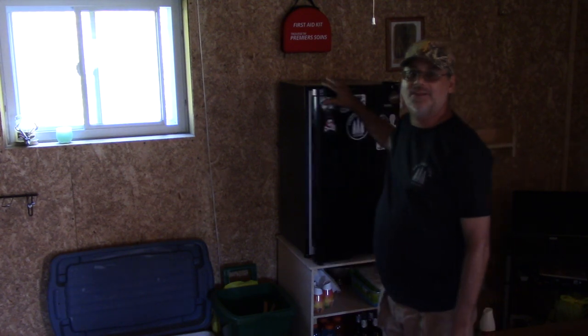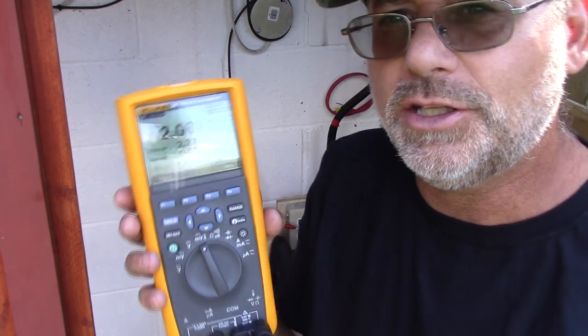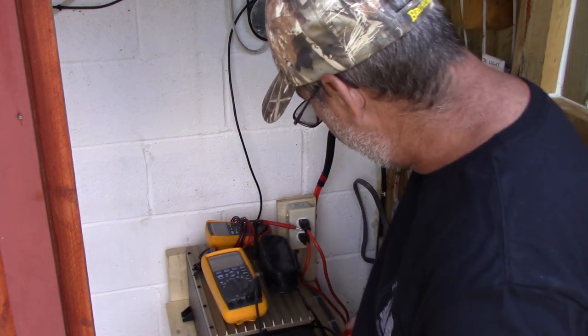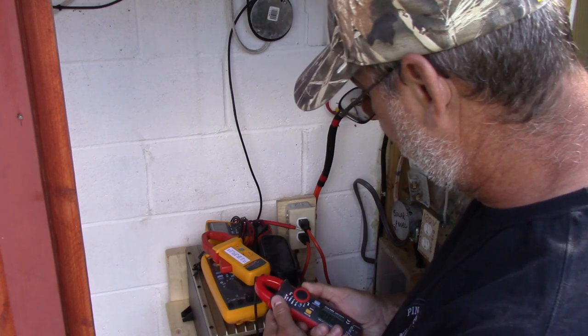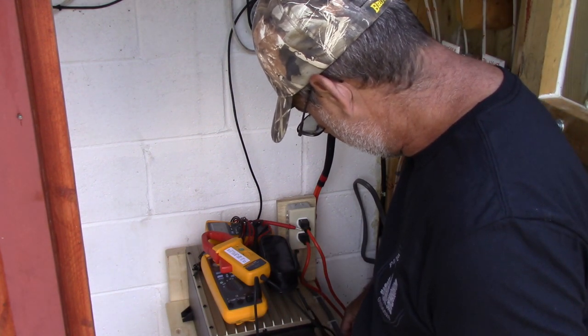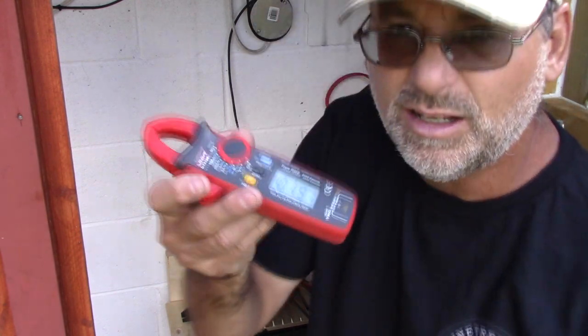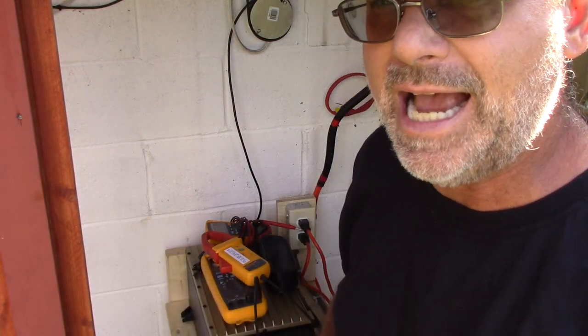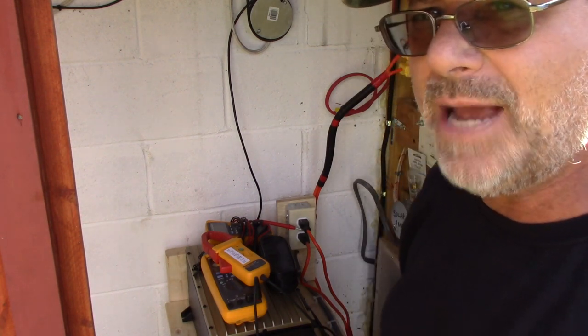It's all loaded up, I got everything in there, it's working great. I'm going to take you out to the control center here and show you the specs. This is with no load on - roughly two amps - and I'll show you the other meter just to verify it. 1.97 amps, I think that says. So the no-load is actually higher than what I was told. I was told it was going to be under an amp. To me it looks like it's two.